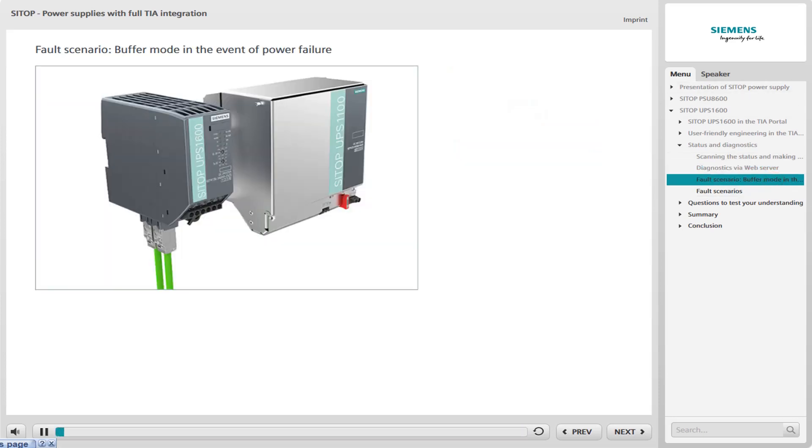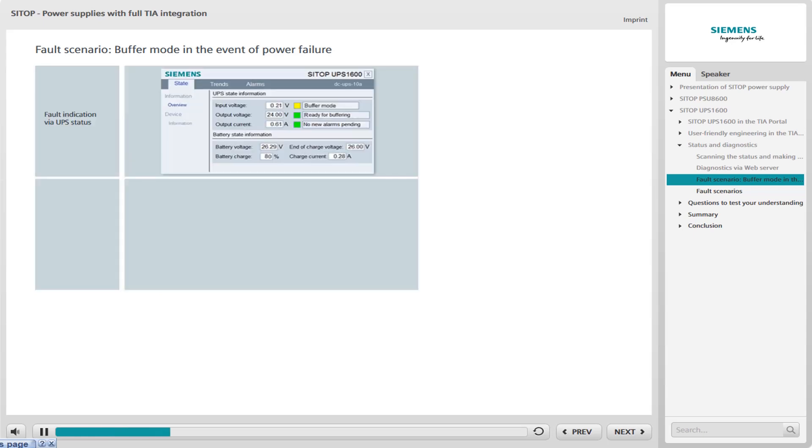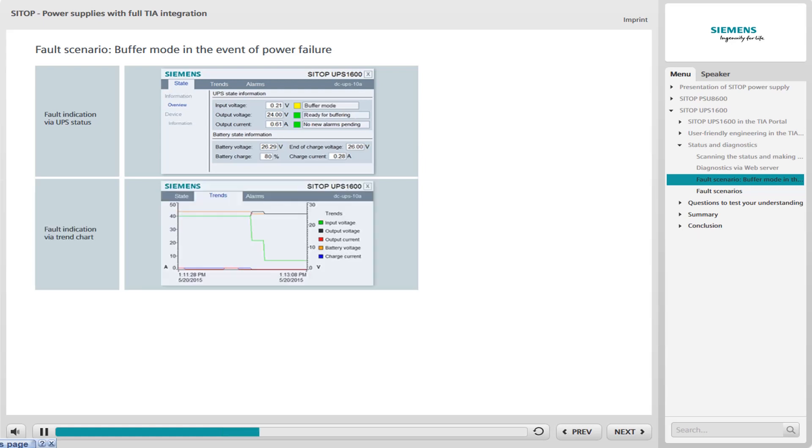Buffer mode in the event of a power failure is a possible scenario for using the UPS 1600. The display of your faceplates shows you the following. As soon as a power failure has been registered, the status of the UPS changes to buffer mode, indicated using an alarm box colored yellow. In the trend chart, it can be seen that the input voltage, represented by the green line, suddenly drops. This shows the time of the power failure.